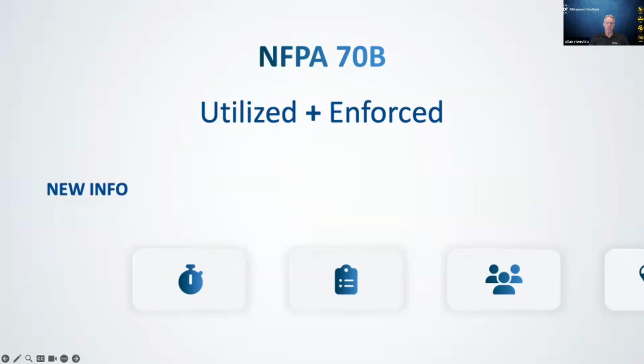Implementing NFPA 70B will improve electrical asset reliability through the following new information and practices. First of all, it outlines the importance of a structured electrical preventative maintenance program for electrical equipment, including transformers, circuit breakers, MCCs, motors, switchgear, substations, anything. Regular maintenance, and that really doesn't tie to certain voltages, high voltage, medium voltage, right across the entire spectrum. Regular maintenance ensures that equipment operates optimally and reduces the likelihood of unexpected failures. Failures that could lead to downtime, failures that could lead to costly repairs or safety incidents or worse.